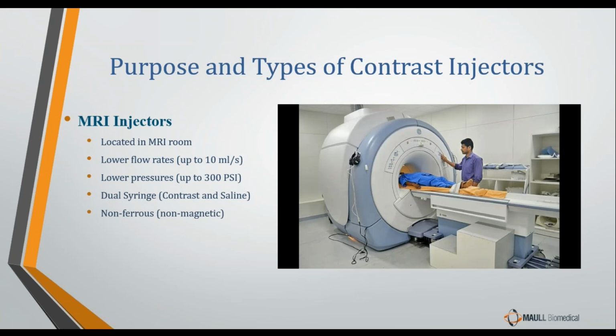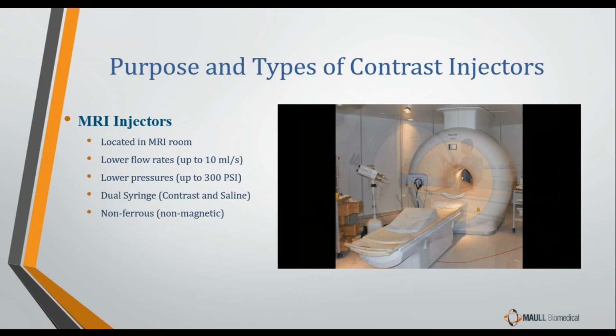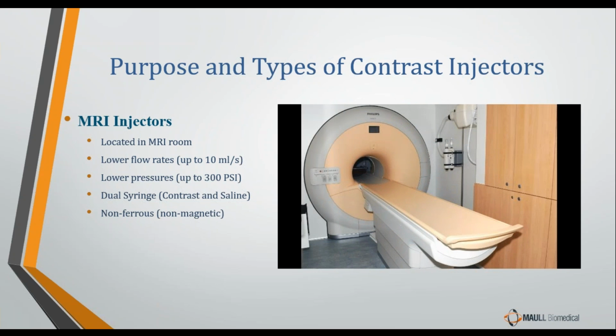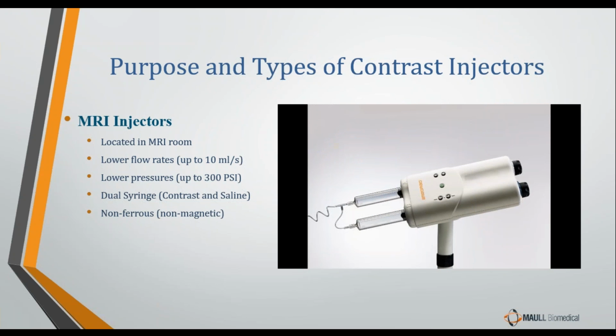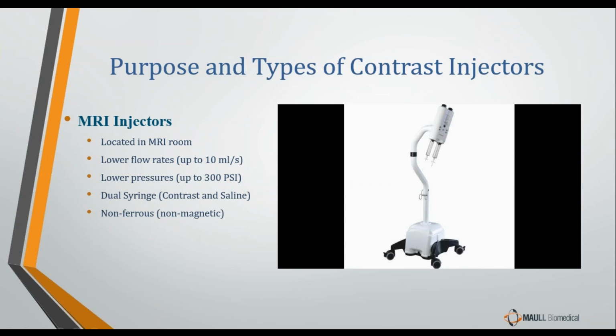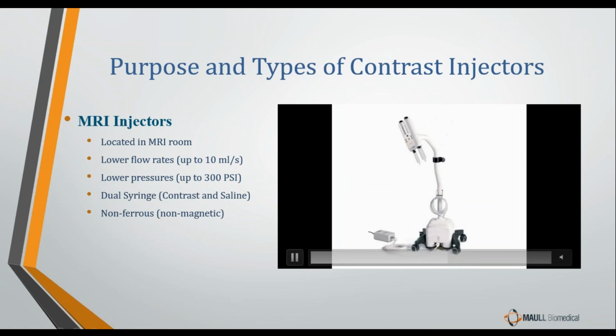Now, finally, the third kind of contrast injector is an MRI injector. MRI injectors are obviously located in the MRI room, and they are very similar to their CT counterpart. They only go up to flow rates of 10 milliliters per second. They only have pressures that go up to as high as 300 psi, and unlike CT injectors, all MRI injectors are dual syringe injectors. They all have a saline syringe and a contrast syringe.